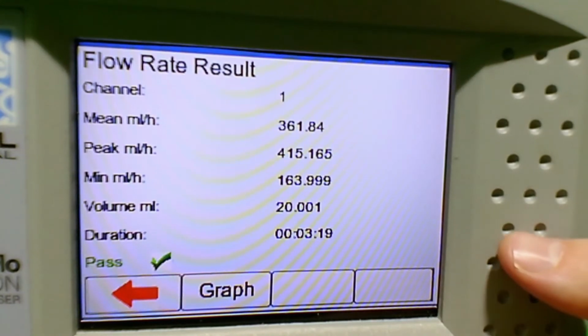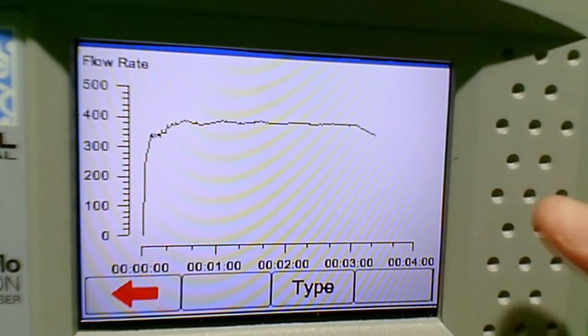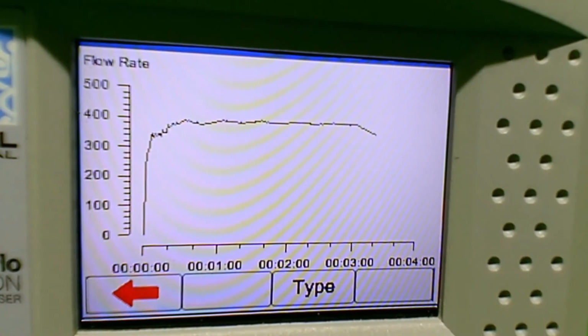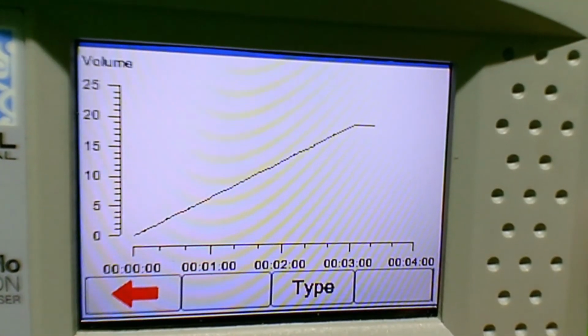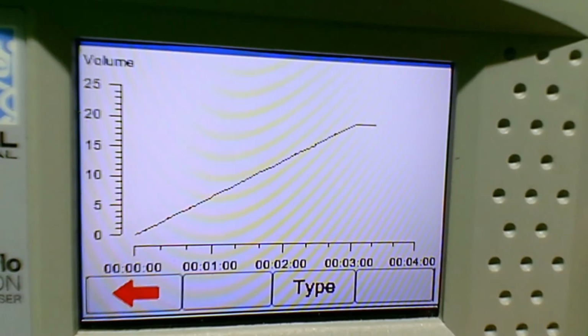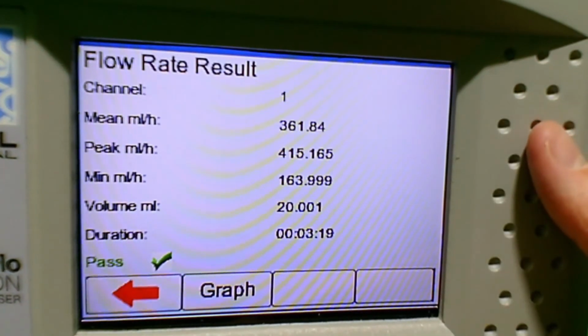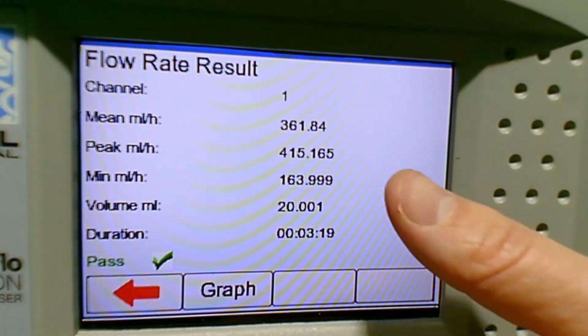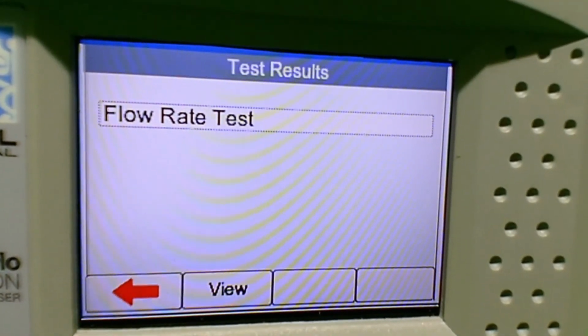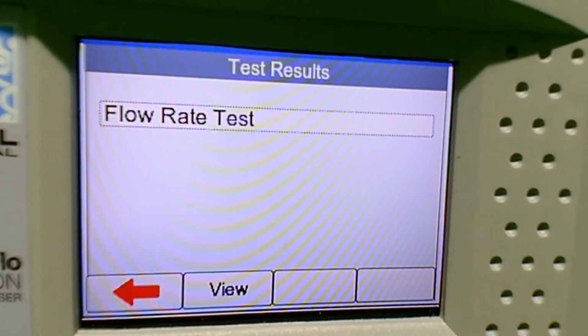Select results, view. 20.001, so I think for the Alaris SE it's a 3% error, so well within specification. It also gives you the graphical representation, so the volume is achieved at the point at the end before we've stopped the test. That's a manual mode test.